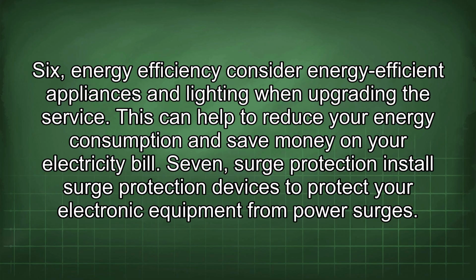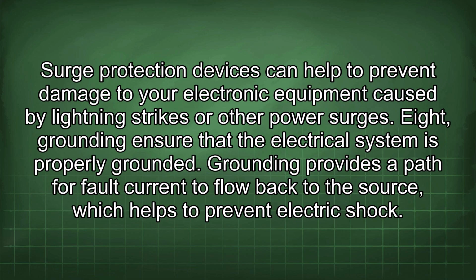6. Energy efficiency. Consider energy efficient appliances and lighting when upgrading the service. This can help to reduce your energy consumption and save money on your electricity bill. 7. Surge protection. Install surge protection devices to protect your electronic equipment from power surges. Surge protection devices can help to prevent damage to your electronic equipment caused by lightning strikes or other power surges. 8. Grounding. Ensure that the electrical system is properly grounded. Grounding provides a path for fault current to flow back to the source, which helps to prevent electric shock.